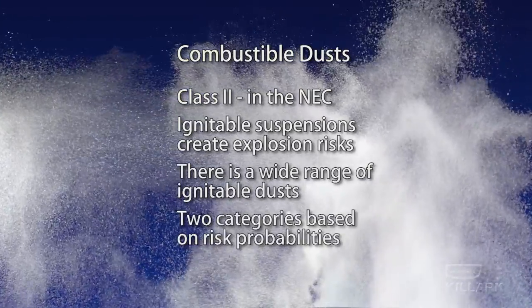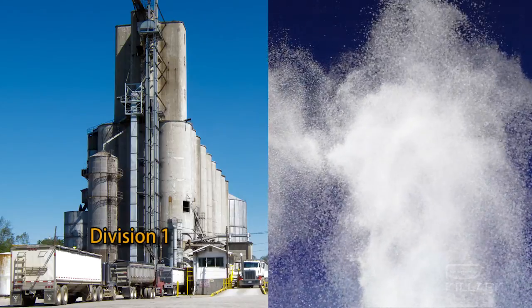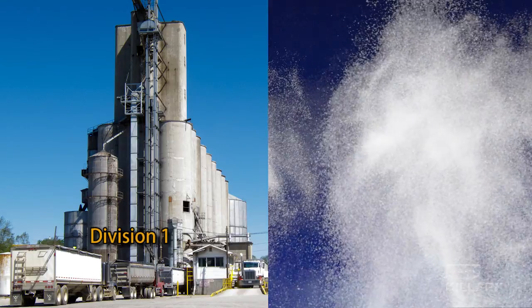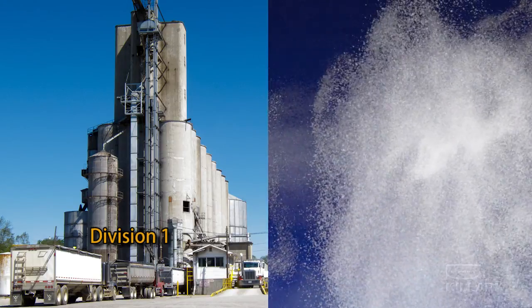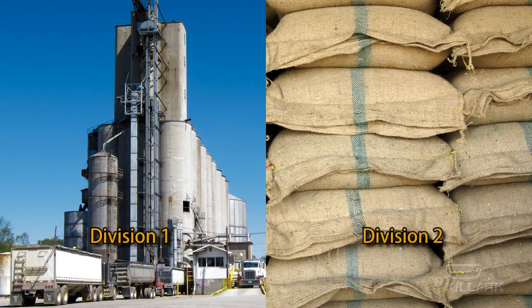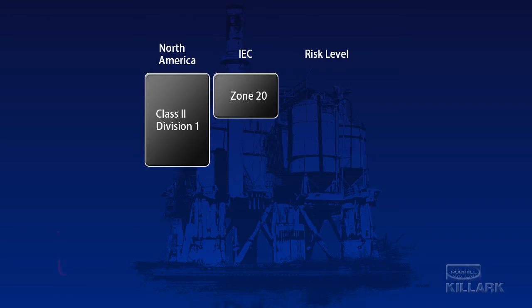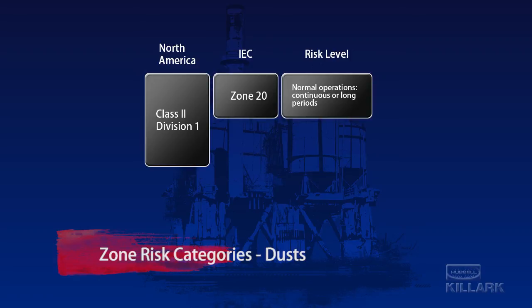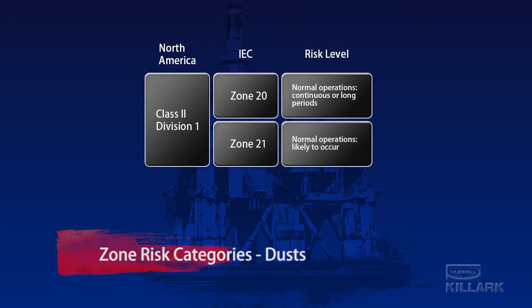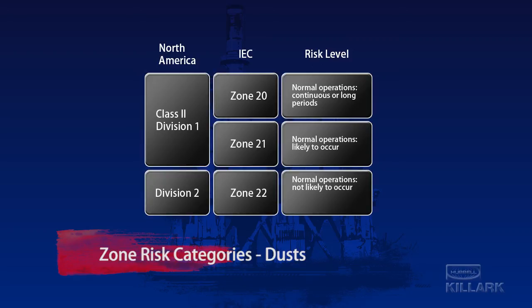The North American system again separates the explosive risks into two divisions. Division 1 is where normal operations could produce an ignitable suspension of dust continuously or at least some of the time. In Division 2, it is unlikely that an explosive concentration of dust would occur during normal operations. Similar to the treatment of gases and vapors, the IEC creates 3 zones for risk assessment. Zone 20 covers risks of ignitable concentrations of dust that normal operations could produce continuously or for long duration. The risk in Zone 21 is considered less severe and is defined as an explosive dust suspension being only likely during normal operations. In Zone 22, the risk of ignitable concentrations is unlikely under normal circumstances, but it's possible that an accident in the storage or handling of the material, for instance, could generate an ignitable cloud.